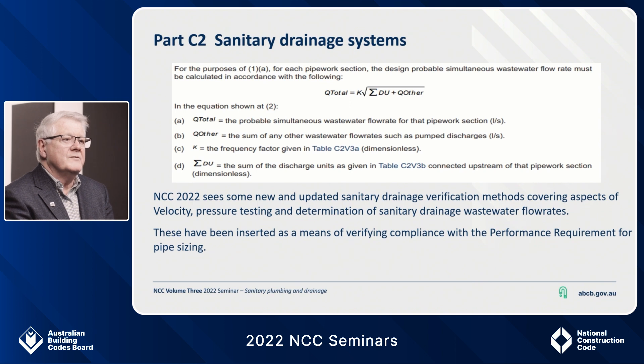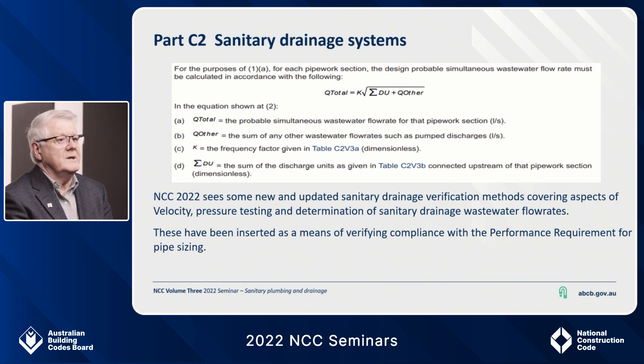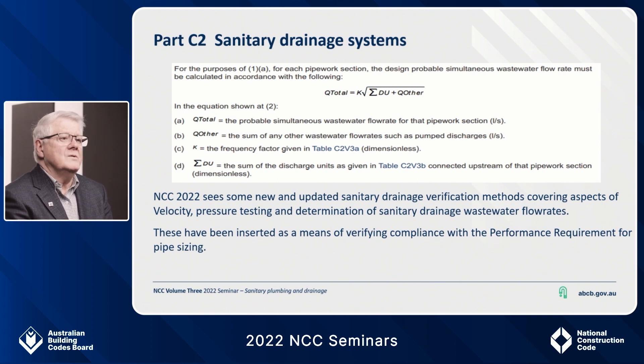In addition to the performance requirements, changes in this part include a new pipe sizing method for sanitary drainage systems through the introduction of new verification methods. The two existing verification methods brought over from 2019 are velocity and liquid-to-air ratio, and pressure testing. The new verification method for 2022 is determination of sanitary drainage wastewater flow rates.